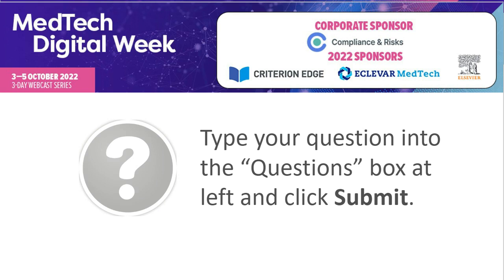Many of our clients have not yet developed safety and performance objectives when it's time to write the CER. And your safety and performance objectives are the way that you measure the effectiveness of your clinical data on your device. So the safety and performance objectives should be identified early on in your design phase and your device phase, during the development. What are you developing that device to do? What is its intended purpose? Thus, how would you measure the safety and performance of the device for its intended purpose?